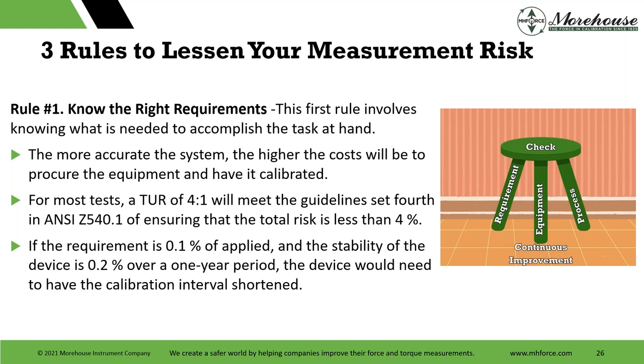Then I bring back TUR — four-to-one, four times greater. The origins of that are from the Navy and Jerry Hayes. Paul Reese and John Harbin did a paper and found that regardless of your reliability, a TUR of 4.6 to 1 was the magic number. What's super amazing is how close Jerry Hayes was in 1955 — back then, drawing a risk curve could take a week, and we can draw one now in a couple of minutes with MathCAD, MATLAB, or Excel.